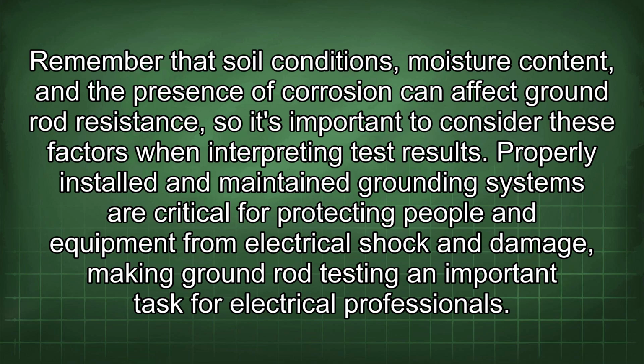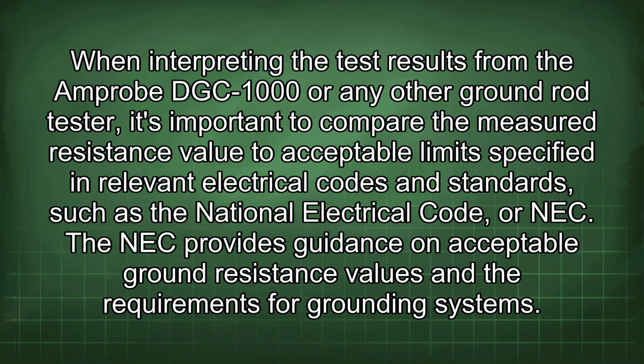Properly installed and maintained grounding systems are critical for protecting people and equipment from electrical shock and damage, making ground rod testing an important task for electrical professionals. When interpreting the test results from the Amprobe DGC-1000 or any other ground rod tester, it's important to compare the measured resistance value to acceptable limits specified in relevant electrical codes and standards, such as the National Electrical Code, or NEC. The NEC provides guidance on acceptable ground resistance values and the requirements for grounding systems.